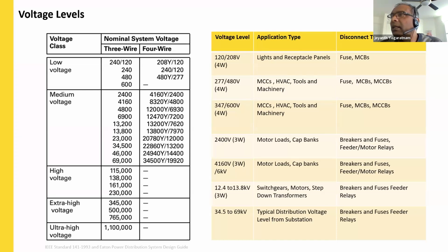Let's look at the loads and what protection devices are typically used at these low and medium voltage levels. When it comes to low voltage applications, the loads are typically service loads, such as fire system, security system, etc., motor control center loads, low voltage motors, light loads, receptacle loads, and HVAC load applications. The protections are provided for the circuit using fuses, MCBs, and MCCBs.